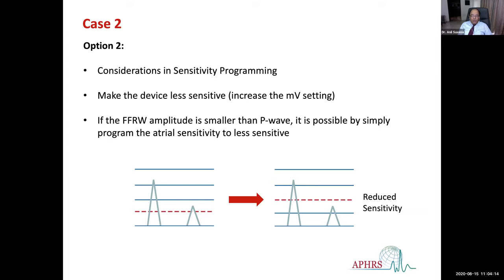The second way to solve this problem is if the atrial signal is taller than the ventricular signal, and the sensitivity setting is quite high so that both are being sensed, we can reduce the sensitivity by programming a higher millivolt value. This will allow us to sense only the atrial signal, and the ventricular signal will not be sensed, so the count will not be doubled. That can be another way.